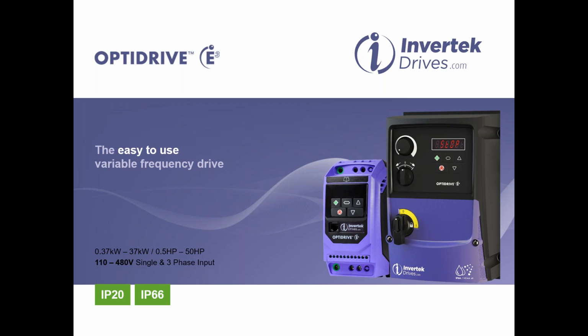So the E3, this is our easy to use entry-level product, so general purpose, with a power range from 0.37 kilowatt up to 37 kilowatts, so half a horsepower up to 50 horsepower. We have several different supply options, so everything from single phase 110 all the way up to three phase 480. So we can do single phase or three phase input. And we have two enclosure types. There's the IP20, which is supposed to go into a control cabinet, and an IP66 unit, which doesn't need to be in an enclosure at all.